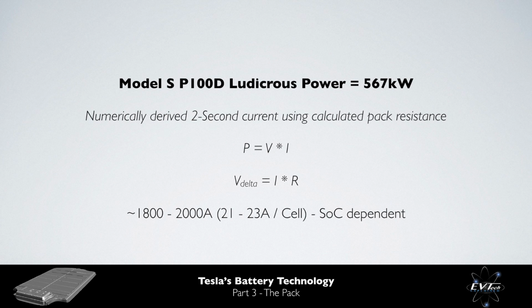With this information, we can derive that at a maximum power output of 567 kilowatts, our pack current will be 1800 to 2000 amps, depending upon state of charge and cell temperature. This results in a cell current of 21 to 23 amps, which is equivalent to 6.2 to 6.7 C per cell as a short duration peak power.